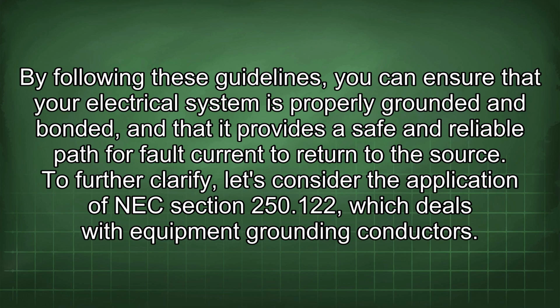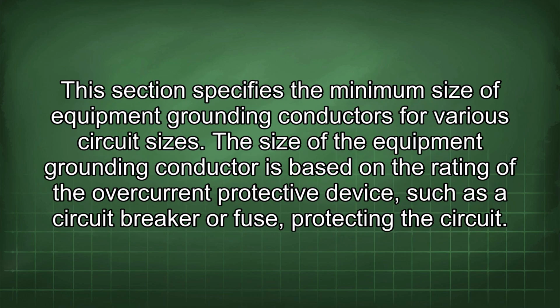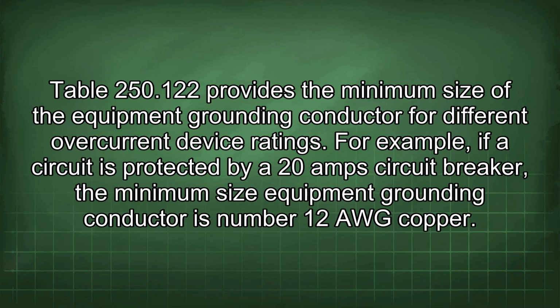To further clarify, let's consider the application of NEC section 250.122, which deals with equipment grounding conductors. This section specifies the minimum size of equipment grounding conductors for various circuit sizes. The size of the equipment grounding conductor is based on the rating of the overcurrent protective device, such as a circuit breaker or fuse, protecting the circuit. Table 250.122 provides the minimum size of the equipment grounding conductor for different overcurrent device ratings.